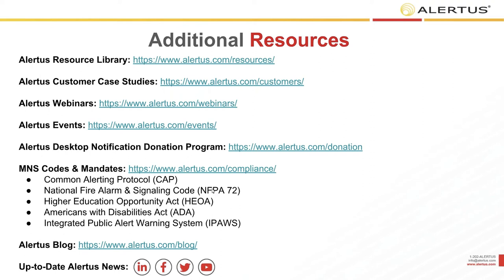Is the Alertus fire panel interface UL listed? Absolutely. Many customers came to us asking about this, especially for the voice notification capability — you're connecting the fire panel with a dry contact and also an audio input. Even though it's not 100% required that the device be UL certified, we went ahead and obtained UL certification for that audio input, which is UL 864. So that device is certified to connect, and we can show that UL certification to your AHJ or fire marshal if required. Some say they're not concerned about it; others want to see the UL listing to ensure it's been tested and vetted.